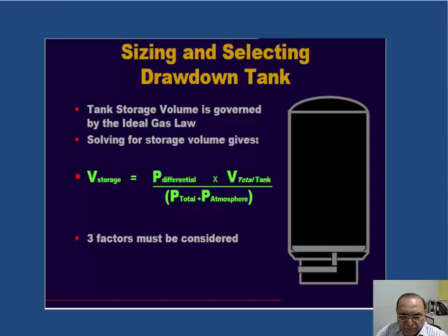How are those things selected? Those things are selected on the basis of water storage. Generally, this storage is required for about 2 to 3 minutes of pump run.